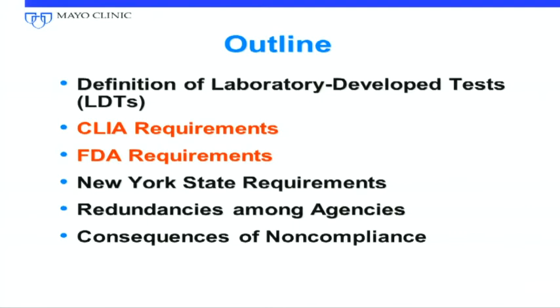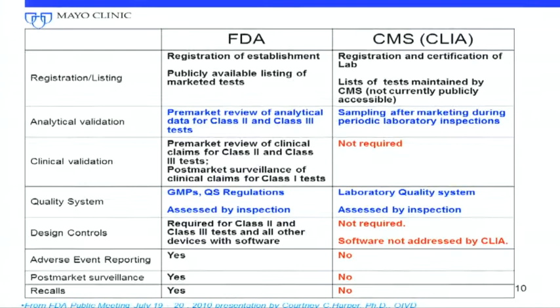CLIA requirements for analytical validation include accuracy — how close are you to the truth — precision, how many times serially you can get close to that result, reportable range, reference range, analytic specificity, and sensitivity. All of these have to be determined and shown to the clinician. CLIA does not mandate that we determine clinical sensitivity and specificity — that's the FDA's domain. CAP, the College of American Pathologists, has deemed status with CLIA, and in recent years their molecular checklist is seeing clinical validation requirements appearing, which signals CMS is also becoming interested.